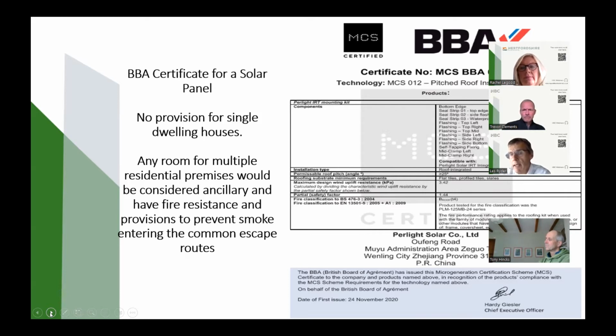of the boundary. Now, there are certain solar panels. Trevor and myself had many a conversation when this first kicked off. We'd more or less considered solar panels located on flat roofs, which are not part of the roof construction, as fixtures, just the same as the air source heat pumps. We wouldn't look at the air source heat pump and look for a roof designation on that. But on the solar panels, my philosophy is, and I think it's backed up by the fact that they are testing them for BS 13501 and obtaining roof designations for them.